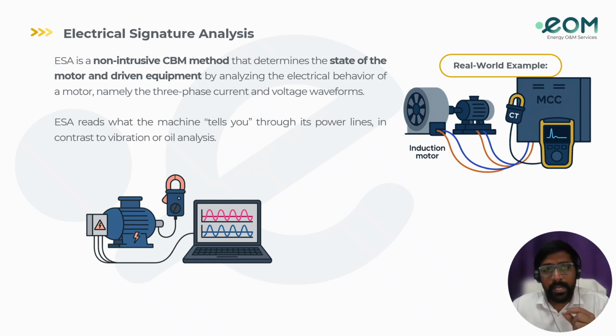Here, as per ISO 20958, it is dedicated to the ESA standard for three-phase induction motors, and it explains techniques like signature analysis and the cautions for VFDs as well. And according to ISO 17359, which gives the general CBM program framework, we need to follow it around electrical signature analysis.